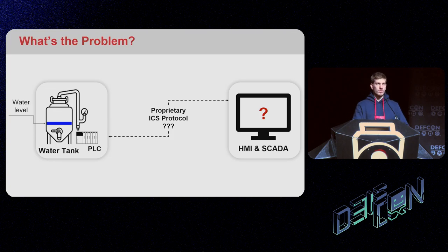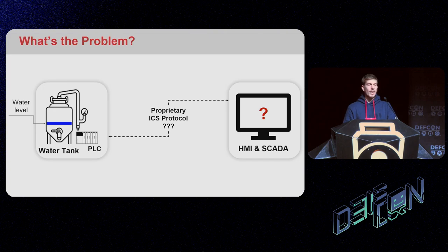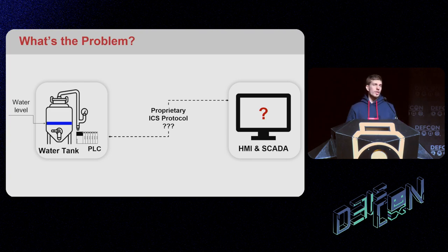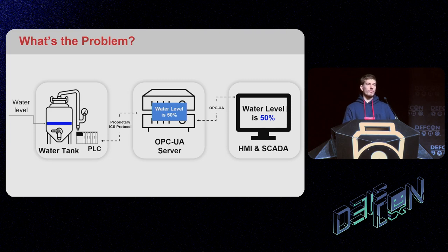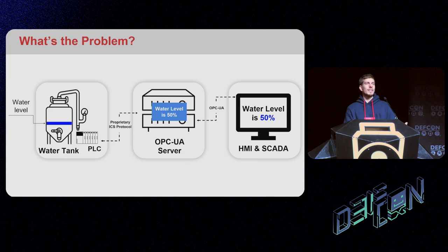These are configured as variables — the sensor reads where the water level is and we have a variable that changes in the process. If we want to monitor this procedure, from an HMI or a SCADA server, we had to use a specific proprietary ICS protocol to communicate with the PLC to read and write these tag values. That's not very convenient if you want different products to communicate with it. OPC UA was introduced to have a unified way to communicate between different devices and products within a SCADA network.